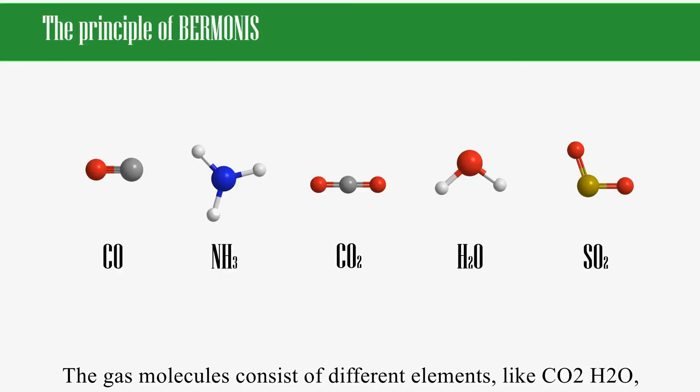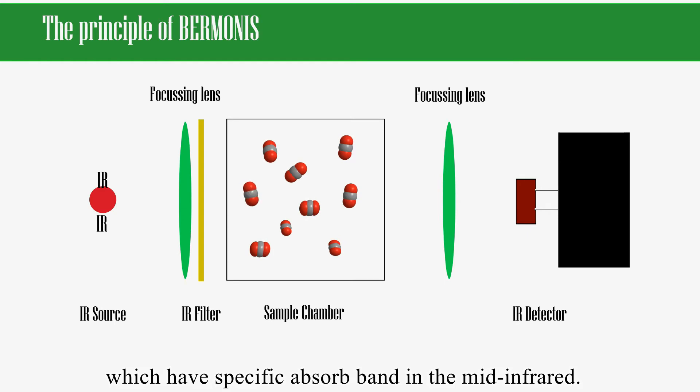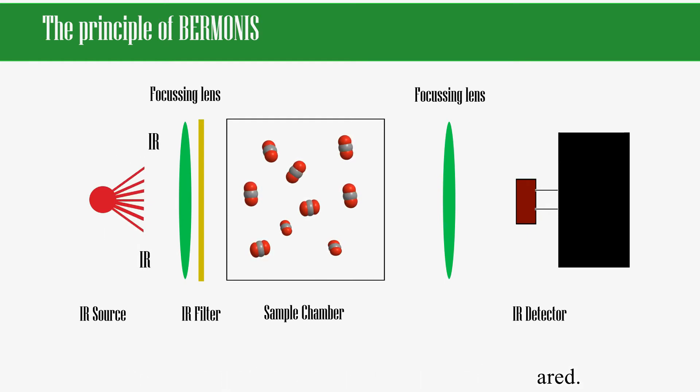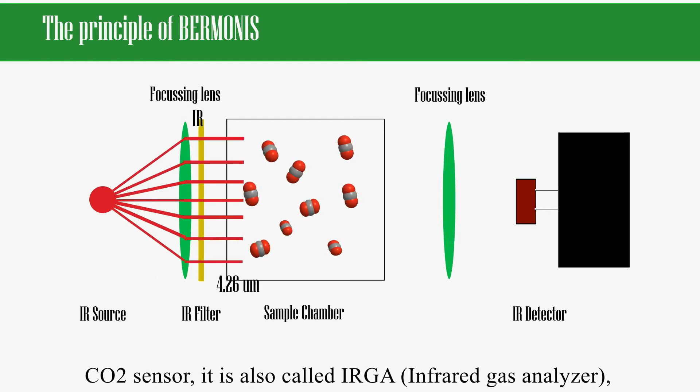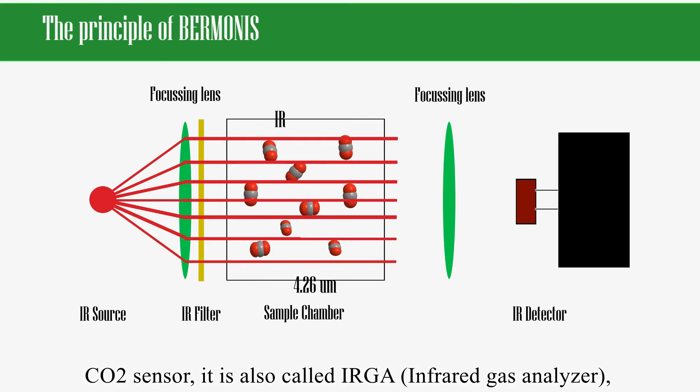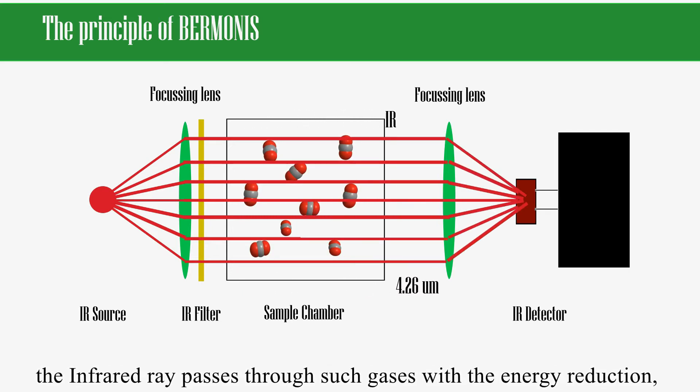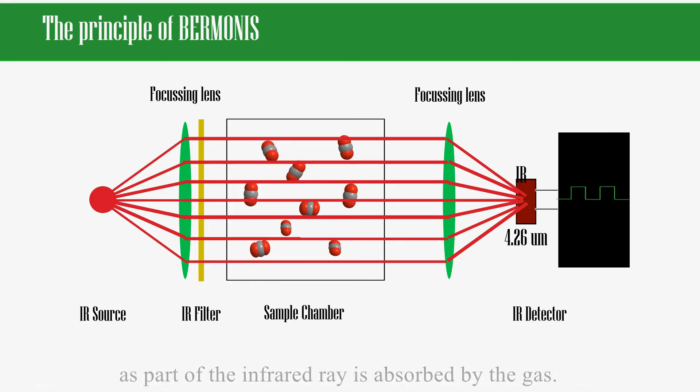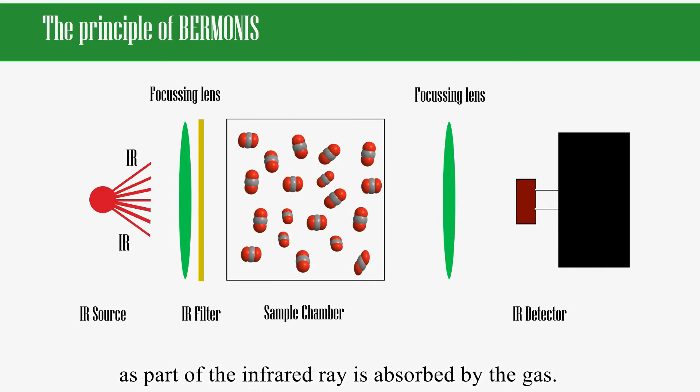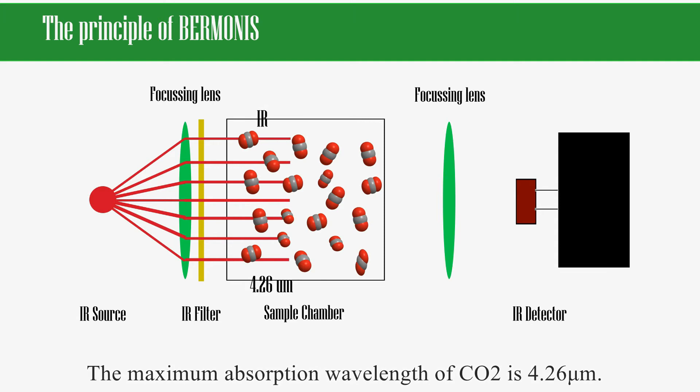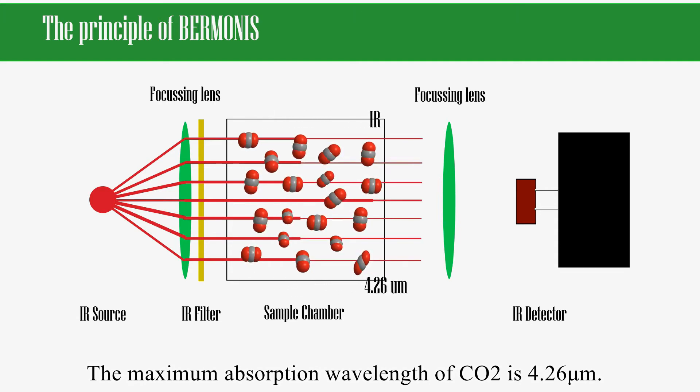The gas molecules consist of different elements like CO2 and water, which have specific absorption bands in the mid-infrared. The CO2 sensor is also called infrared gas analyzer. The infrared ray passes through such gases with energy reduction, as part of the infrared ray is absorbed by the gas. The maximum absorption wavelength of CO2 is 4.26 micrometers.